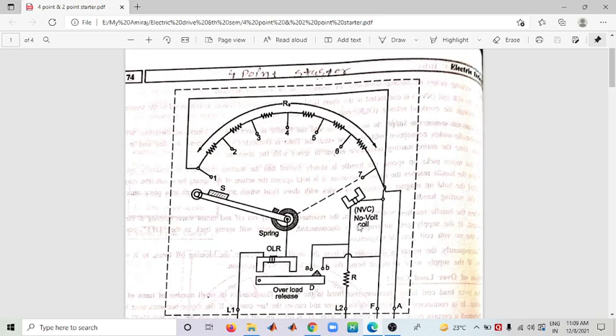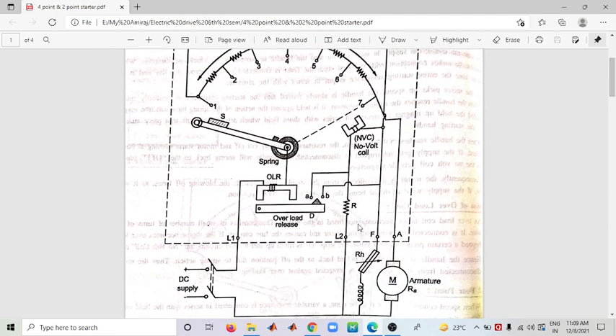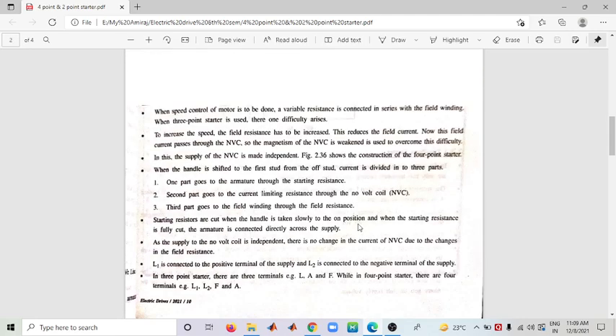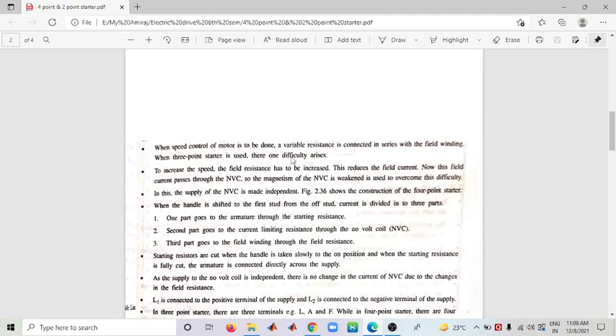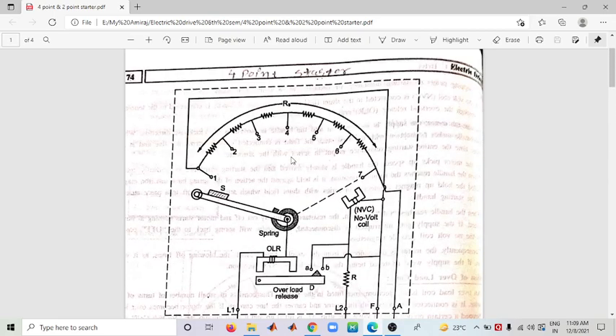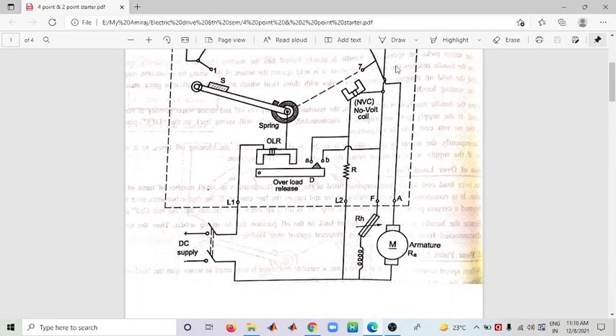When field current is reduced, the magnetism of the NVC will also reduce. To overcome this difficulty, in the Four Point Starter, the NVC is made independent of the field circuit — the NVC is connected independently.